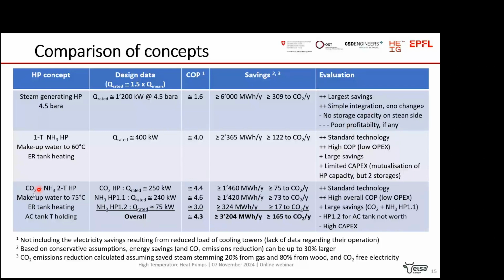If I now compare this to the solution I just described, with the combined transcritical CO2 heat pump and ammonia heat pump with two temperatures, we have a high overall COP with good savings. The benefits are standard technology and high overall COP, so low OPEX.